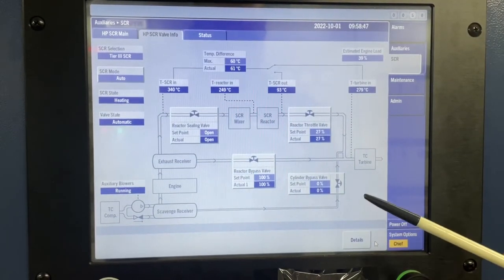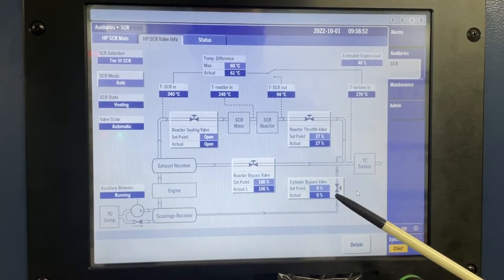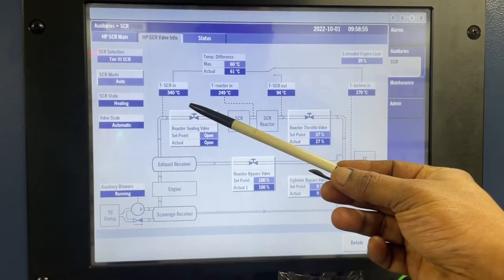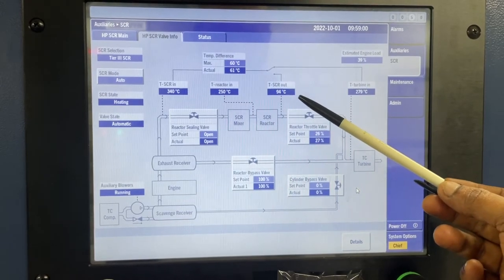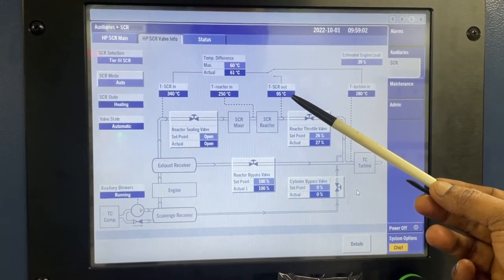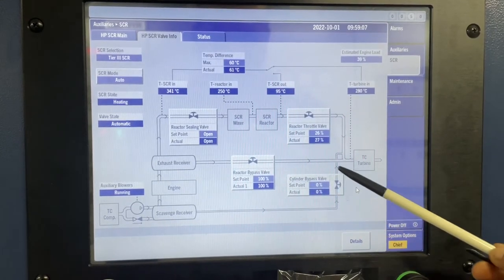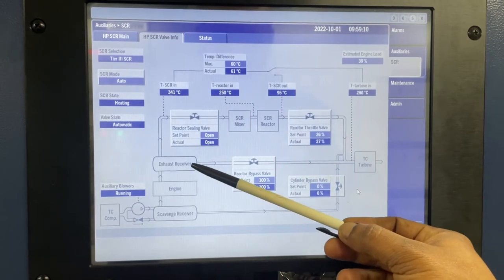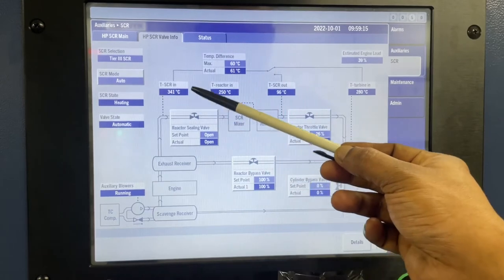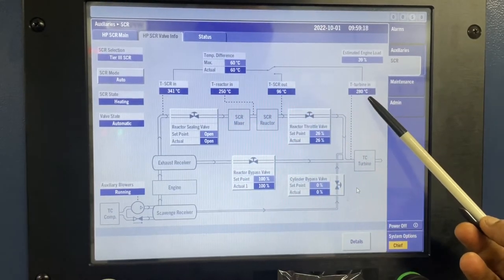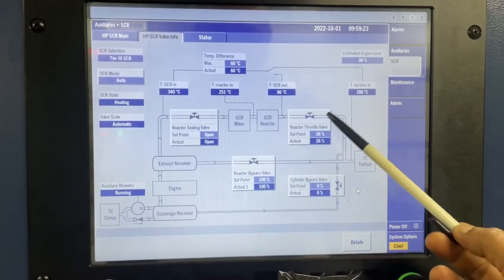Engineers, when CBV is not opening, the temperature difference calculation is taken between the SCR reactor inlet and turbocharger turbine inlet. When the CBV opens, fresh cold air from the scavenger receiver goes to the turbocharger turbine inlet, so the actual temperature difference between the SCR reactor inlet and turbocharger turbine inlet will exceed the predefined value. Then the SCR valve control will activate and start to close the RTV.